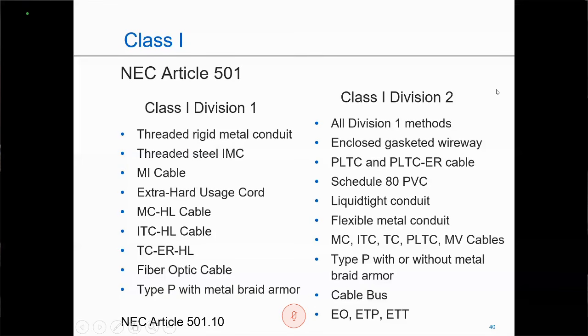Now, when it comes to Class 1, Division 2, all of my Division 1 wiring methods are approved and actually sometimes required. If I were to have an explosion-proof motor starter in my Class 1, Division 2 area, the raceway between that motor starter and my sealing fitting has to be the Division 1 wiring method. After the sealing fitting is when I can start using the less stringent Class 1, Division 2 wiring methods, where you may see things such as liquid tight flexible metal conduit, enclosed and gasketed wireway. You'll notice my cables no longer have the HL designation, which was the designation for Division 1.